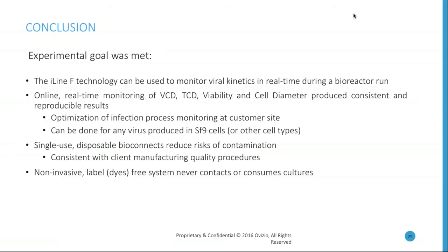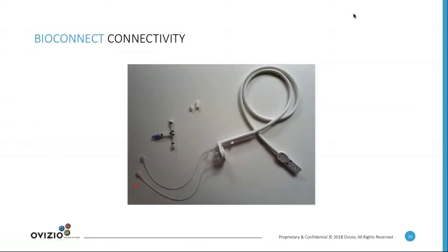The BioConnect — the single-use disposable sampling probe — heavily reduces the risk of contamination, consistent with client manufacturing quality procedures. We use a non-invasive, label-free and dye-free system that never comes in contact with or consumes any of the culture or cells. We have also upgraded our BioConnect, and as of now we can connect our sampling probe to any type of bioreactor using luer locks or C-flex weldable tubing, meaning there is no limitation on the bioreactor type.